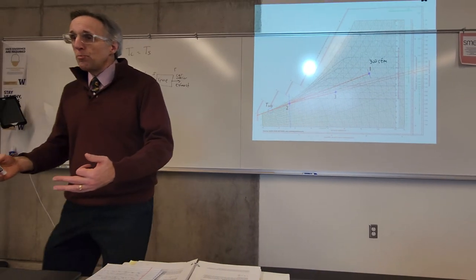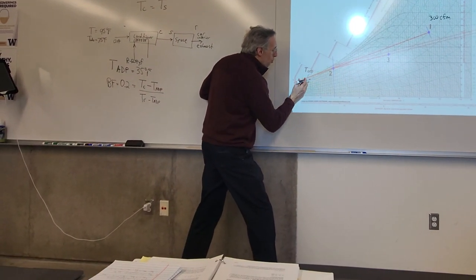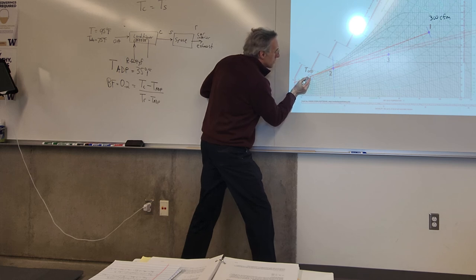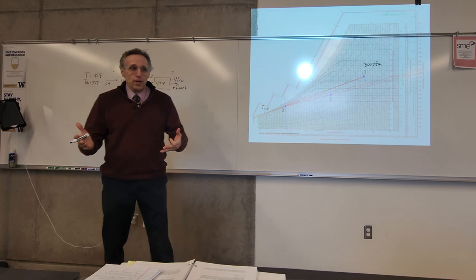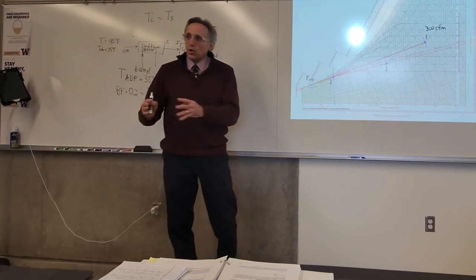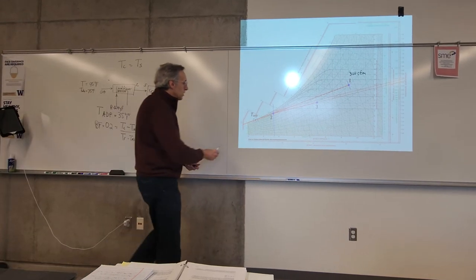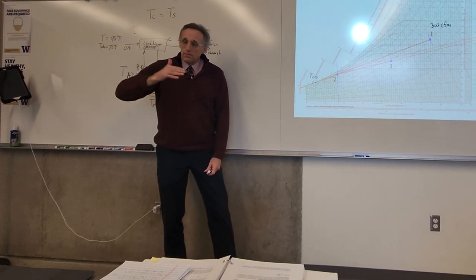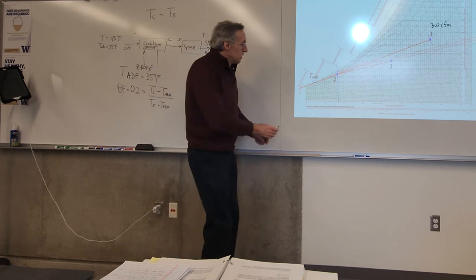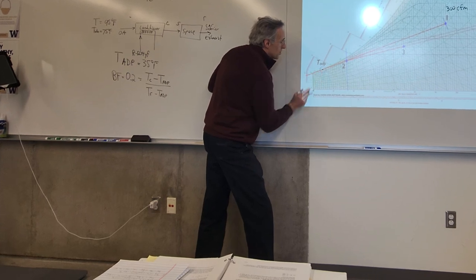Now, what do we do with the apparatus dew point? We plot it. So we come over here and we go all the way out. The apparatus dew point is the temperature on the coil when the cooling coil is operating as it's designed to operate. This is the temperature on the surface of that coil. And you've got cold refrigerant going through there. Refrigerant's probably 20 degrees Fahrenheit. So heat is transferring from outside the cooling tubes to inside the coil. But on the outside surface, this apparatus dew point, that's the temperature on the outside surface of the coil.